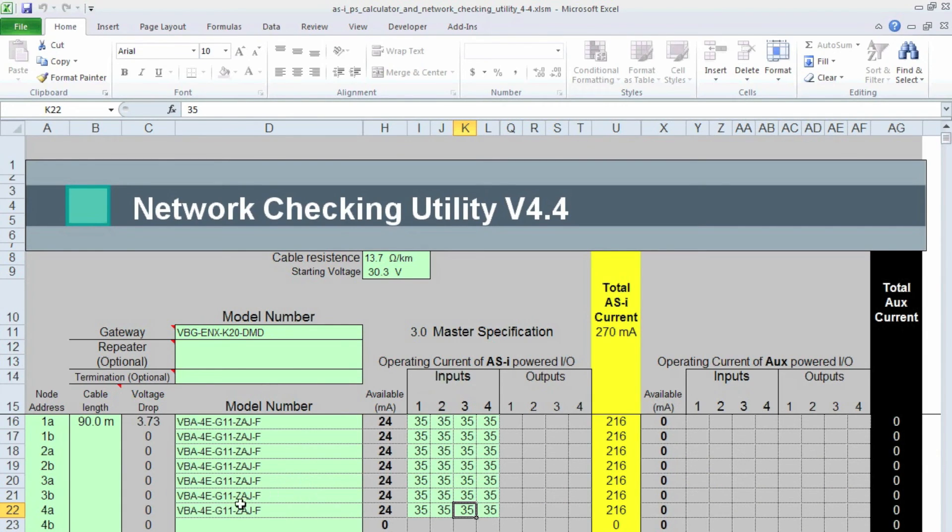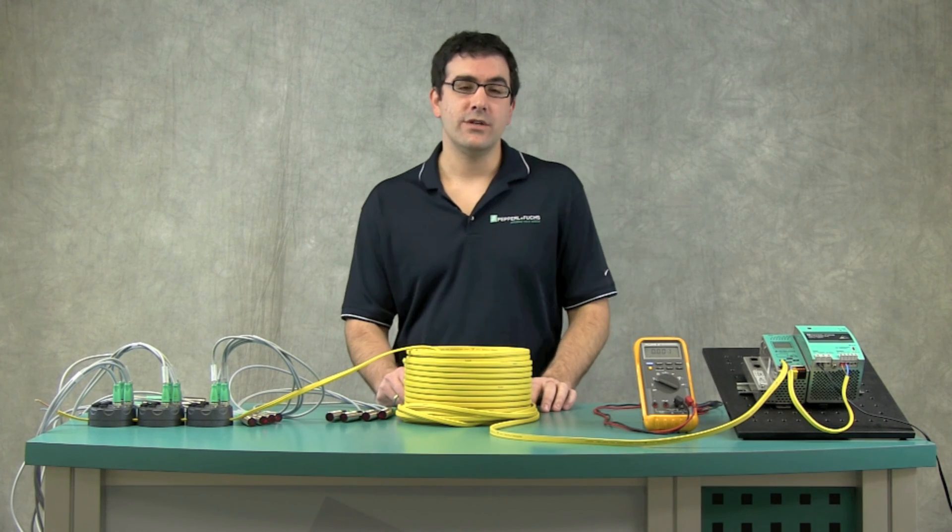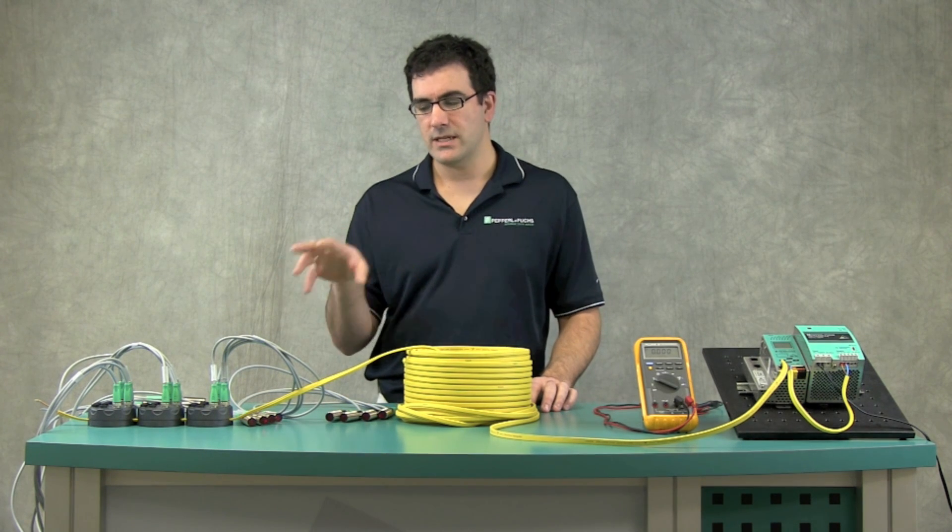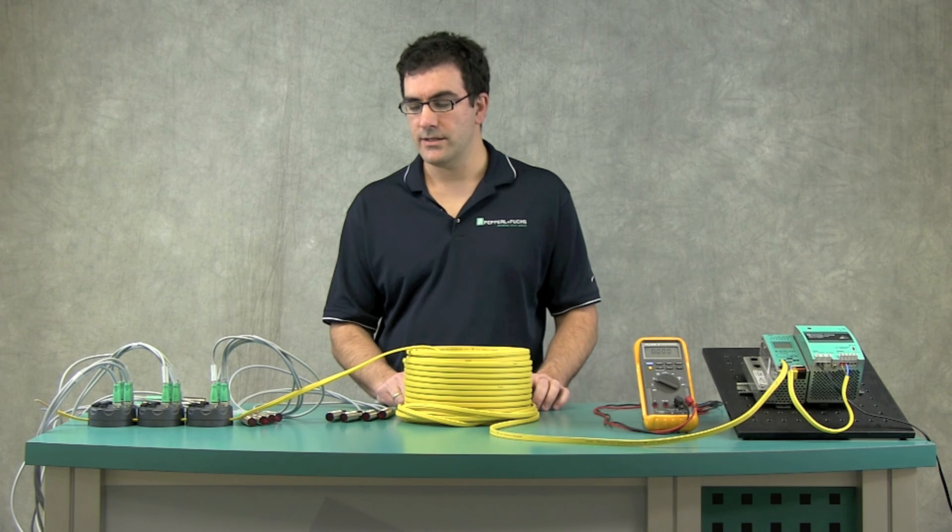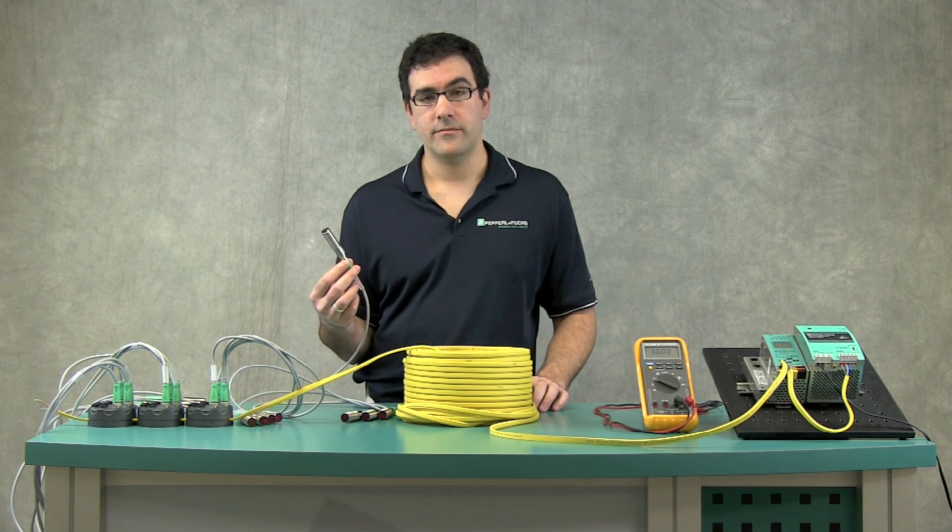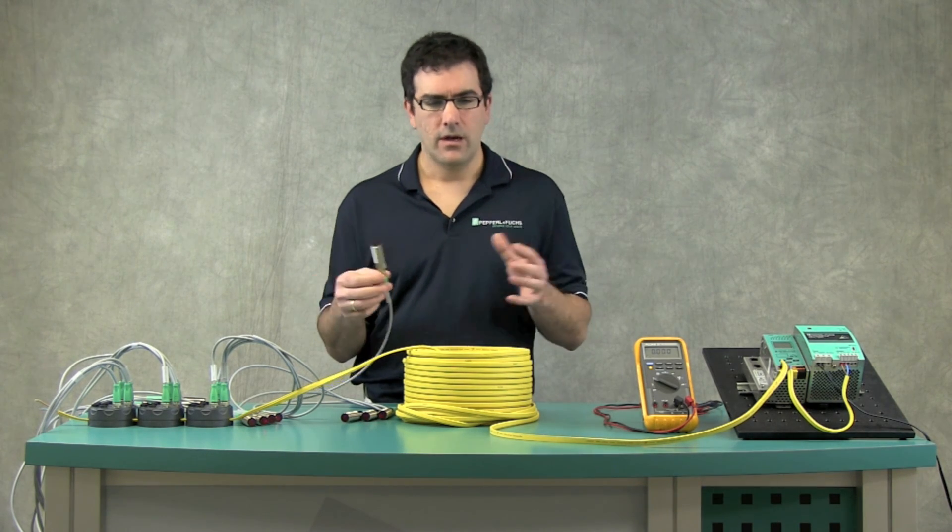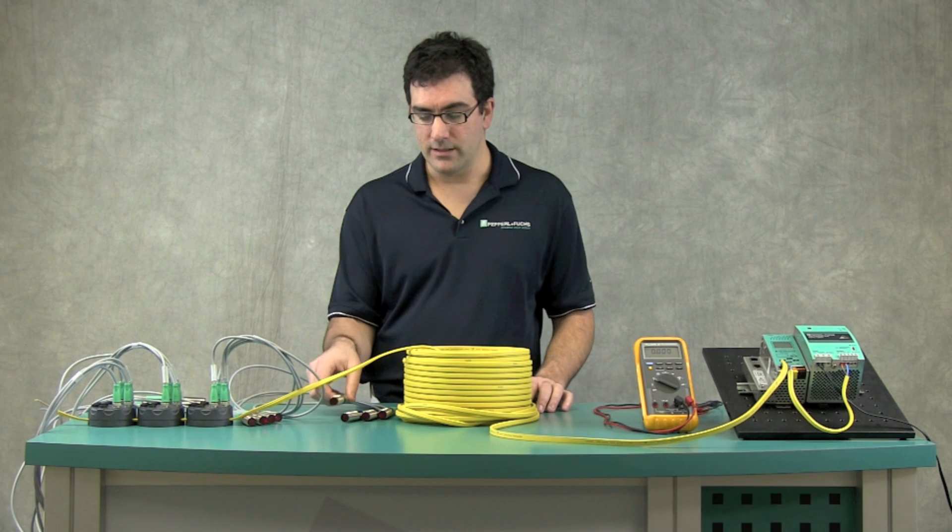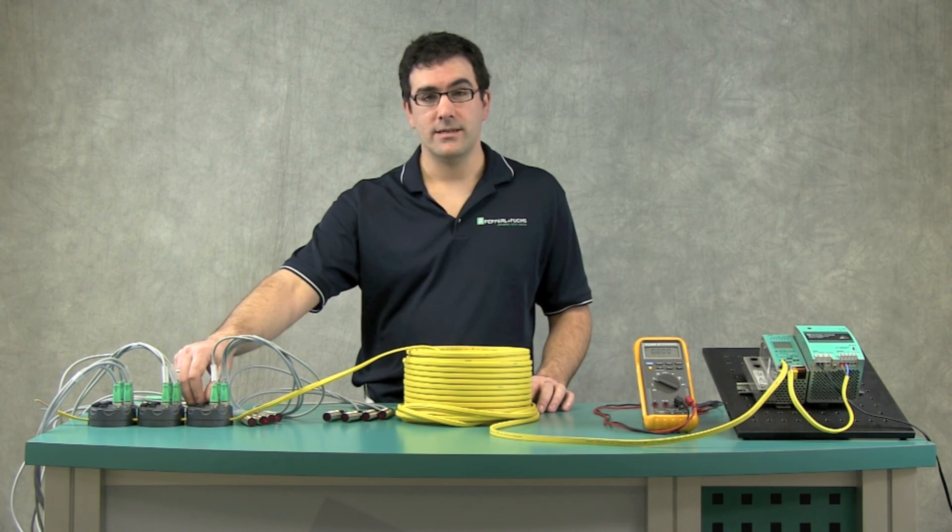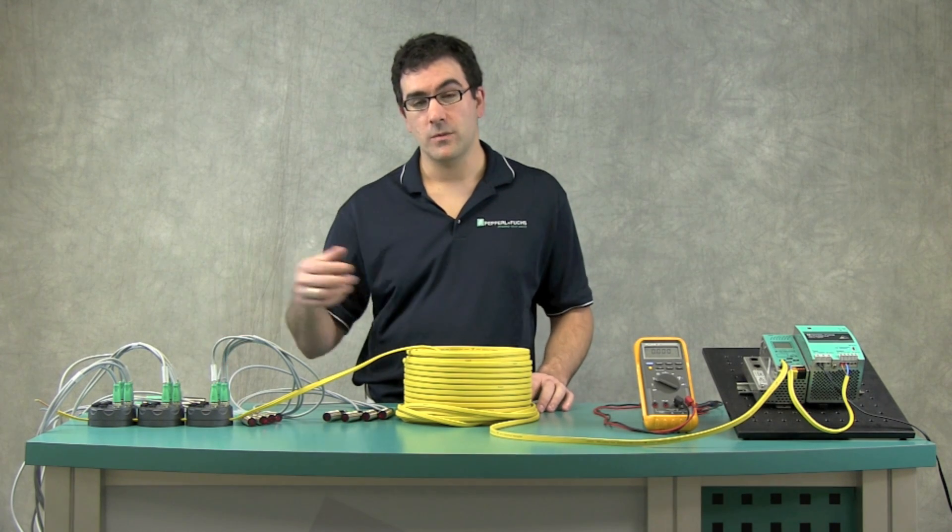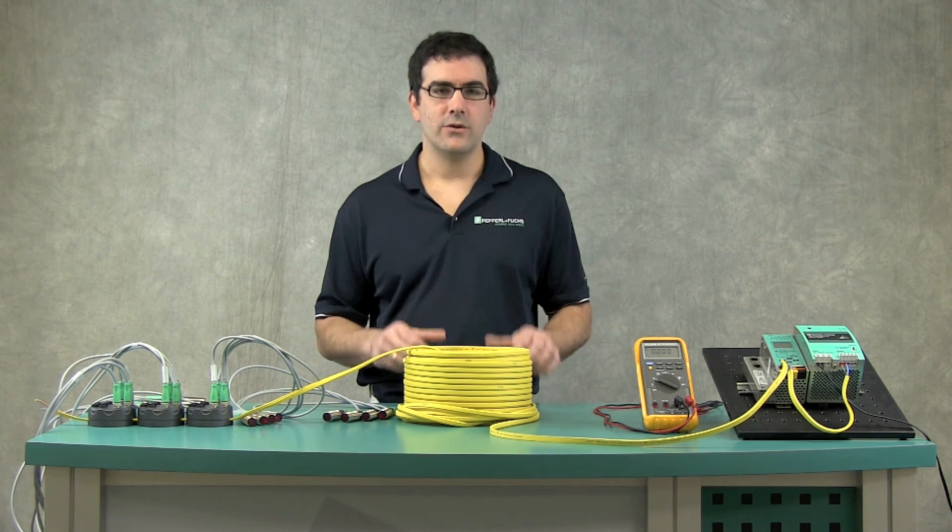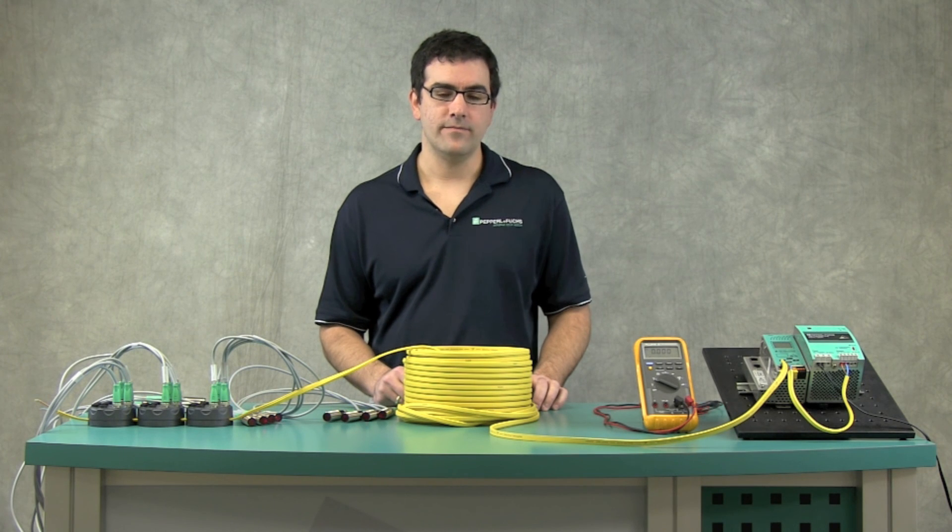So, there you have it. That's the voltage drop and that's the ASI network layout that I can have. Okay, now that we've done the voltage drop calculation on the AS interface power calculator, you'll notice that that voltage drop is a little bit more than what we do in the measured case. That is simply because the no-load operating current is higher than actually measured here. To compensate for overall temperature ranges, it could be a little bit higher. And the same with the ASI module. You'll notice that on the data sheet, it says something like 40 milliamps, and the actual measured value is probably only 20 to 25 milliamps. So, these values are a little bit higher, but it's okay. It's more conservative than really what you need. On that note, thank you.